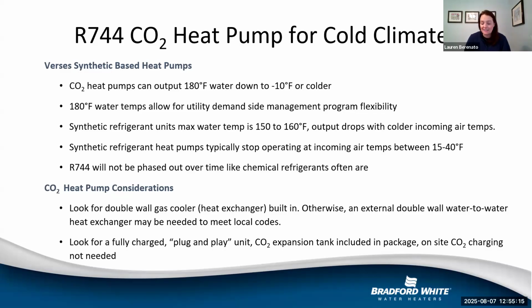Now, one of the things that is a challenge with CO2 units is that if you are servicing them in the field, it does require a contractor that has a certification in operating with CO2 because the pressure is so high. So I don't know if any of you on the call today have already installed these large units. That's the CO2 units that you'll see on the roof of a building because they take up so much space. But something that can be a challenge is having the contractor available to service a system in the field.